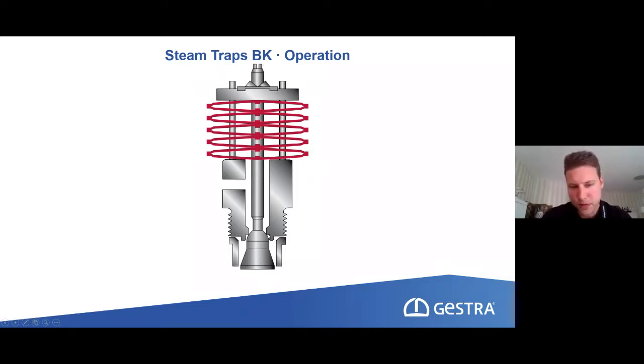What we kept in mind when we thought of the design was that we want to increase the lifetime of such a steam trap, because we want to have it in operation for as much time as possible. So what we have here is a multi-stage pressure reduction. We don't only reduce the pressure on one seat, we have 3 chambers right after each other. The first one is the little chamber here, where we have the first pressure reduction, and some small amounts of flash steam and condensate appear. Then we have a second chamber where we have more flash steam. And then we have a third chamber, in the body, which reduces the rest of the pressure. So a 3-step pressure reduction, which is the best way to go here.